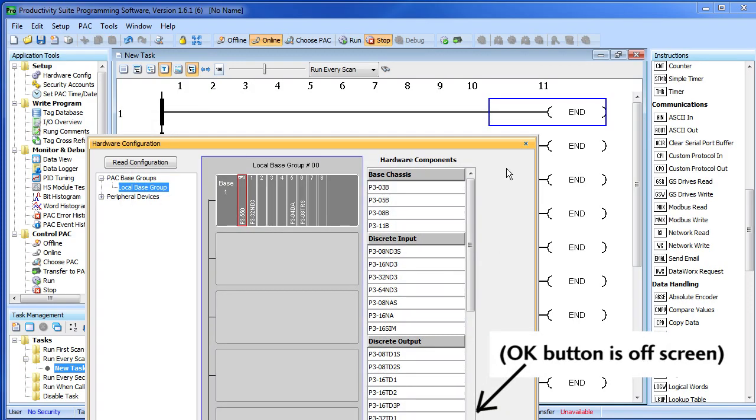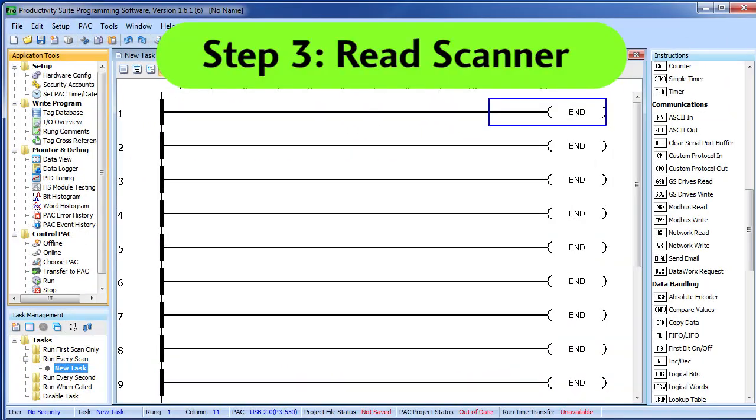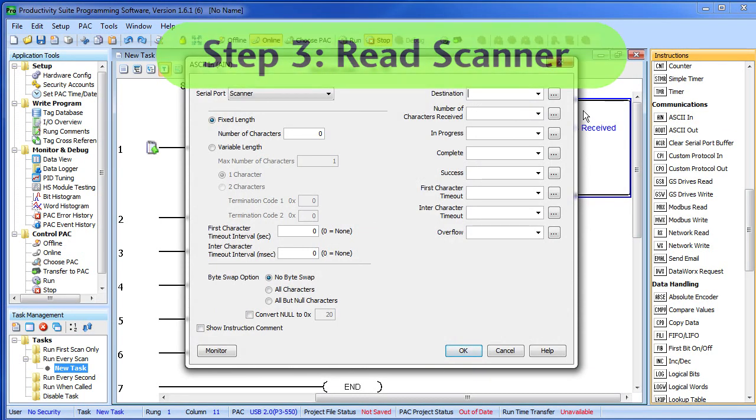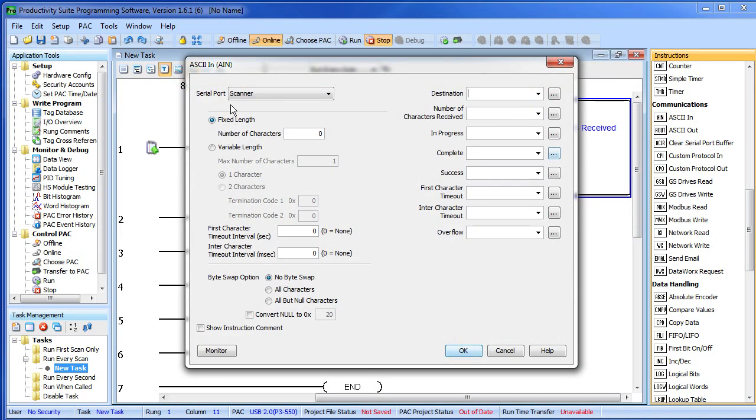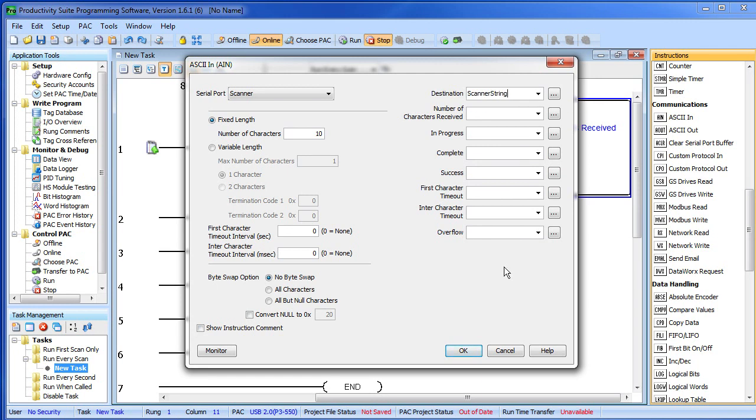OK out of the port window and close the hardware config window. Now we can grab the ASCII IN instruction and just fill in the blanks. The Productivity 3000 software has already filled in the scanner serial port for us because there are no other serial ports. We want a fixed length message—for this example I want 10 characters, you'll see why in a minute—and I just need a place to put the answer. So let's call that scanner string. That's it—that's all we need to do to interface to the scanner.